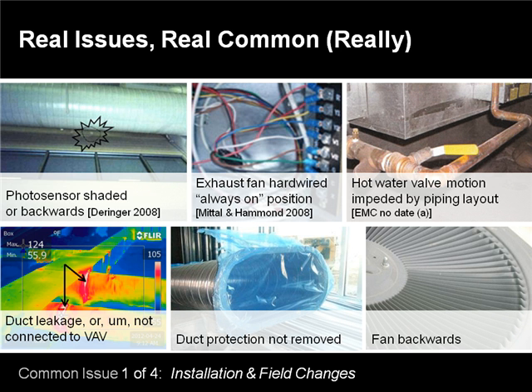So that's part of the serviceability that we look at when we're commissioning jobs, trying to see that it's serviceable equipment and that you can isolate things when you need to. Duct leakage, or sometimes we see ducts that aren't even connected to anything. They just blow off into the ceiling. They're supposed to be connected to a VAV box, and also they leak where the joints come off of the main duct.